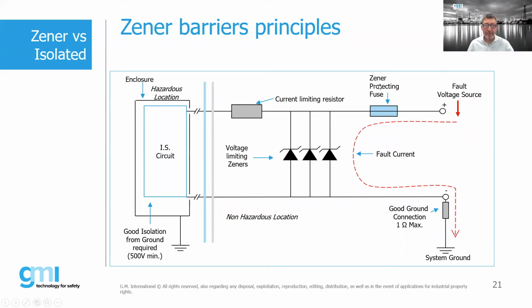You can? Okay. So we have a Zener protecting fuse right here. We have voltage limiting Zener diodes located right here, and we have a current limiting resistor right here. Basically, if we have a fault and the current goes way too high, the fuse could potentially blow. The current limiting resistor is going to limit the amount of power. But as the voltage goes up with the fault current, these Zener diodes will open up, and any of that excess voltage should then be shunted to a system ground.